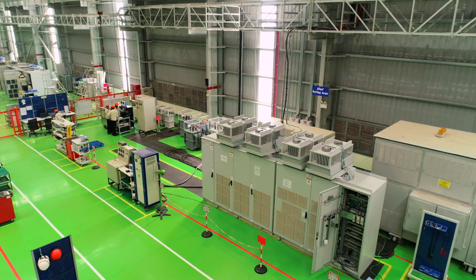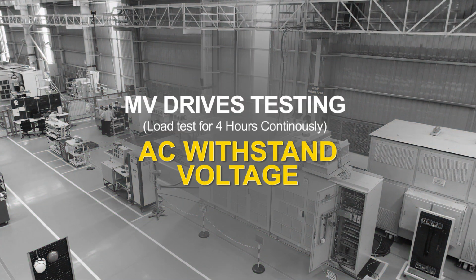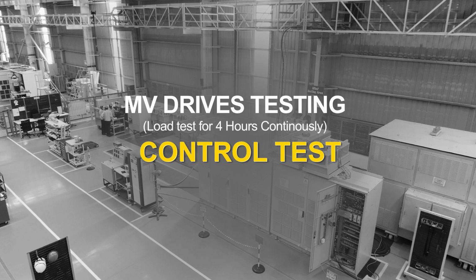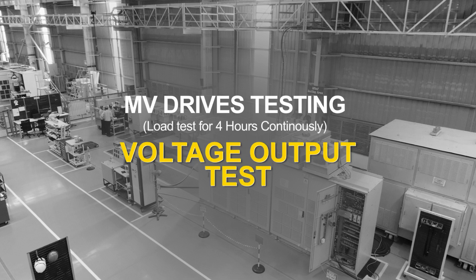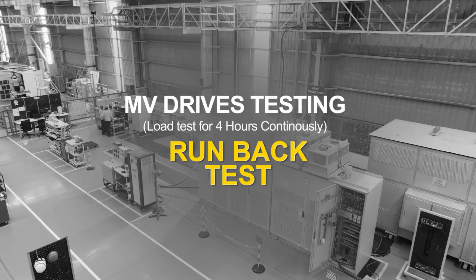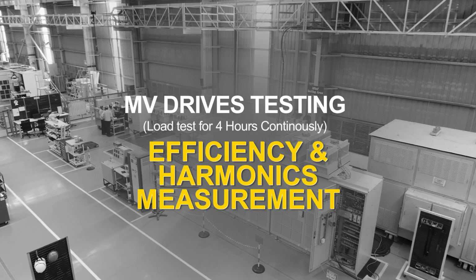Each drive undergoes insulation resistance, AC withstand voltage, control test, logic simulation test, voltage output test, run back test, and efficiency and harmonics measurement.